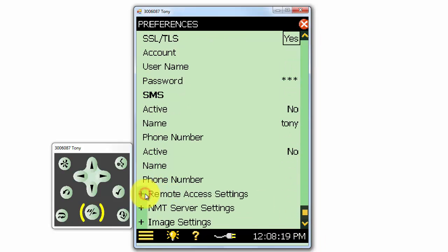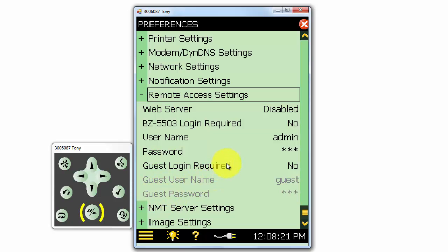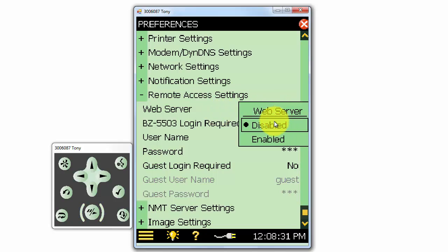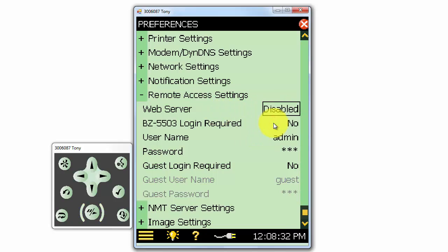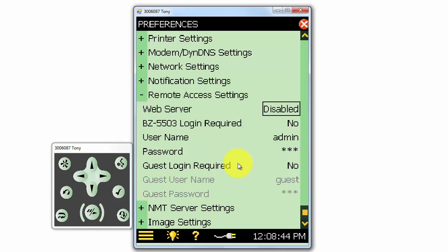If we're connected to a network, we can also allow remote access to the meter by enabling the web server. We can select whether we will require the user to log in through the measurement partner suite software, BZ5503, and what the user name and password will be to access the meter. The guest login will allow someone to log in to view the meter remotely without being able to control it.